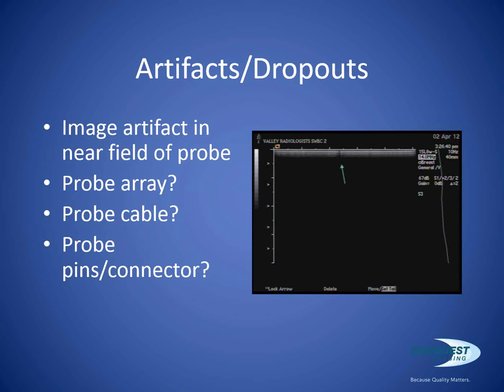The problem happens if somebody bends pins on a probe and doesn't catch it. What happens is then they plug that probe into a system, and now they've damaged the connector board on the system. So now you have a bad probe and you have a bad connector board. But it gets worse. The sonographer will then unplug that probe from that connector and maybe plug another probe into that connector. So now we've damaged another probe. But then it gets worse from there. If it's in a large hospital, what they may do is take one of those probes and move across the hallway and plug one of those probes into another machine, thereby damaging that machine and starting that problem all over again. So we want to make sure, if we do have an artifact or a dropout, that we're examining all the probe pins and the connector board on the system.